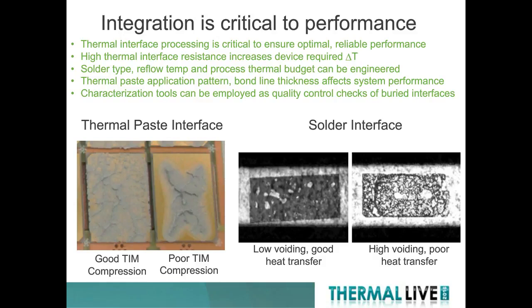So in the end, at Phononic, we take that interface very seriously and actually use automated equipment to define and process that interface. And we often will go back and check our work with characterization tools to inspect buried interfaces that are between two pieces of metal or between the ceramic device and a metal heat exchanger plate.